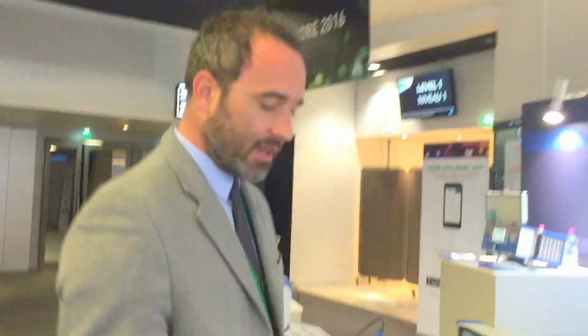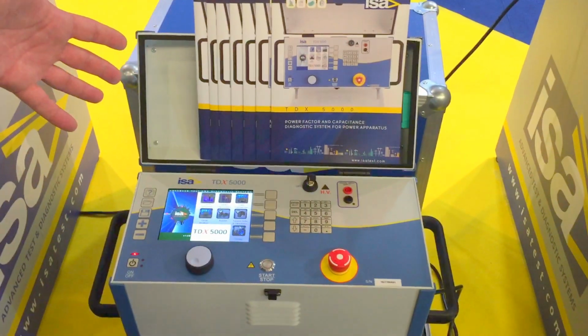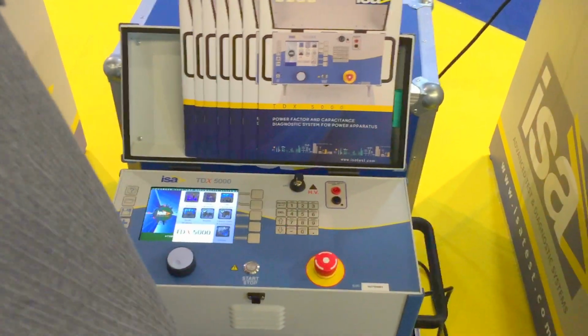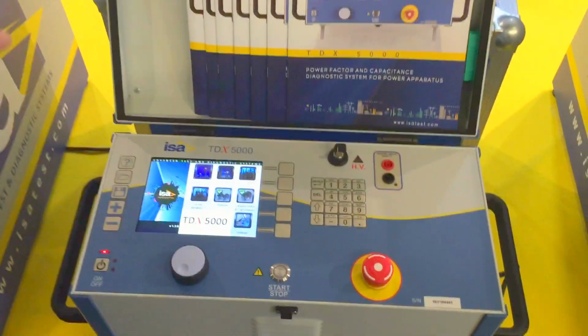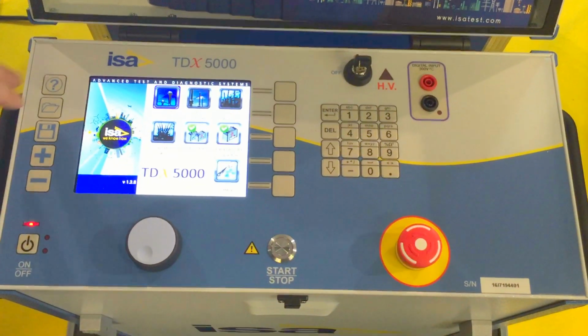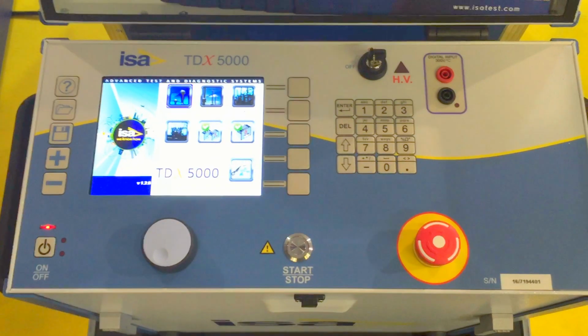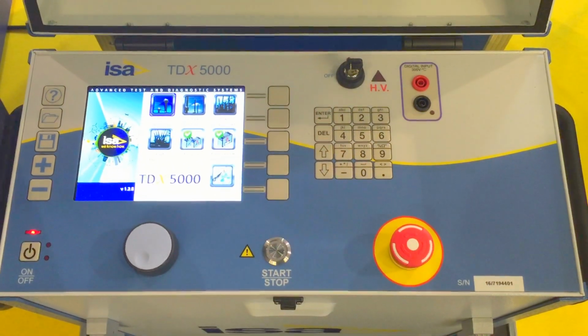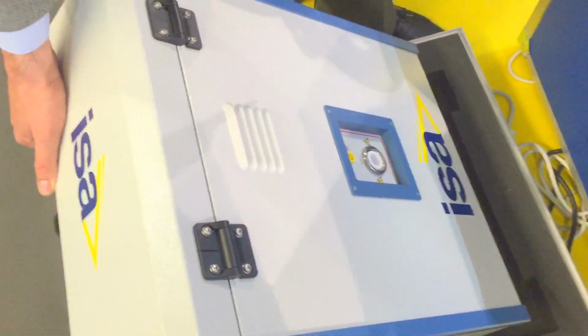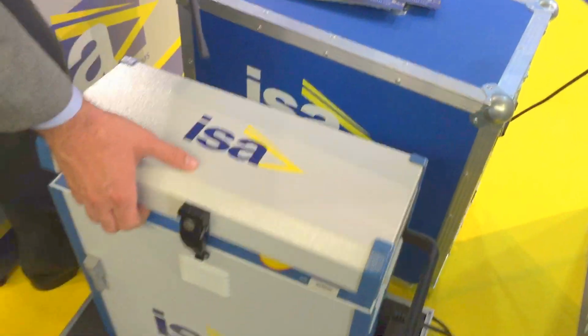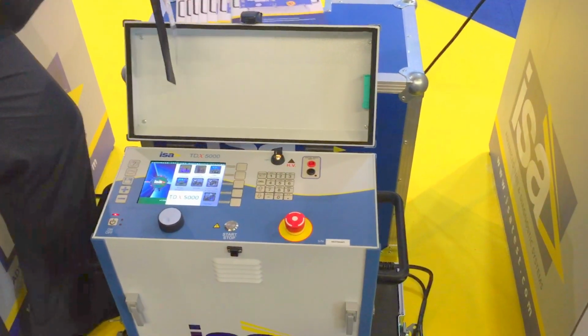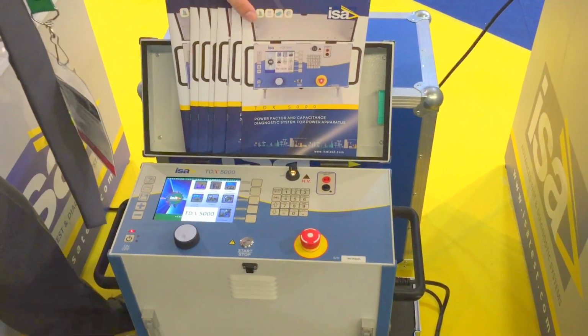Now, a spin-off, this device is a new test set which we call TDX5000. So TDX5000 was created as a marriage between STS5000 and TD5000. So this is a device which does tan delta test, and also you can do a no-load test. It's one box, and I can show you right now here, which can generate up to 12 kilovolt. So you can see the 12 kilovolt output here, and the box itself comes with this nice carry case, so you can take it on a plane. So one box to do your tan delta power factor dissipation factor test.